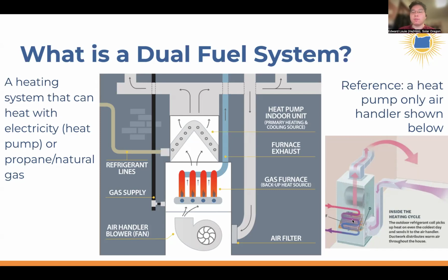Now, in a heat pump only air handler, the components are fewer, and in addition to that, typically in a heat pump only cabinet, the blower is on top of the coil, and the reason for that is you gain a little bit extra efficiency by having the blower on top of the coil so that it's a pull-through air situation. The reason why the blower can be at the bottom and the coil on top in a gas furnace situation is because the gas heat exchanger helps kind of diffuse the air from the blower so that by the time it hits this coil, it's also nice and even, so that there's even airflow across the coil. But when there's no gas heat exchanger and it's just a refrigerant heat exchanger, then a pull-through system allows for more even air to go across that refrigerant coil. So that's why the positioning is a little bit different.